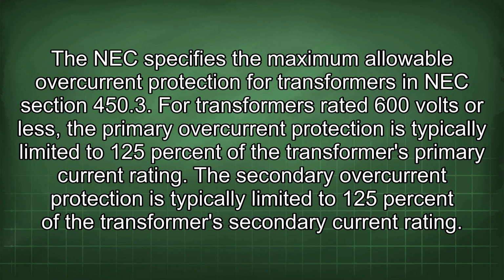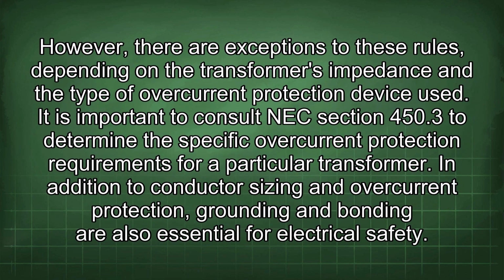For transformers rated 600 volts or less, the primary overcurrent protection is typically limited to 125% of the transformer's primary current rating. The secondary overcurrent protection is typically limited to 125% of the transformer's secondary current rating. However, there are exceptions to these rules, depending on the transformer's impedance and the type of overcurrent protection device used. It is important to consult NEC section 450.3 to determine the specific overcurrent protection requirements for a particular transformer.